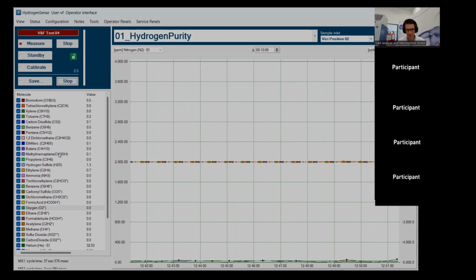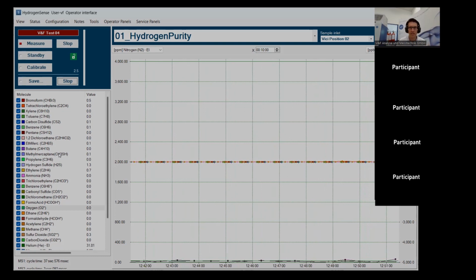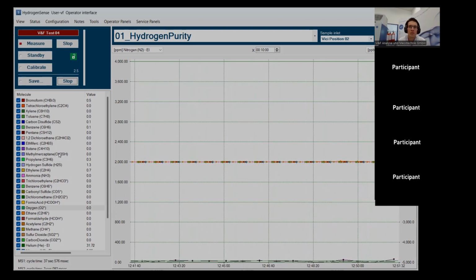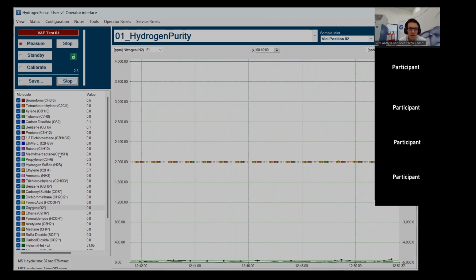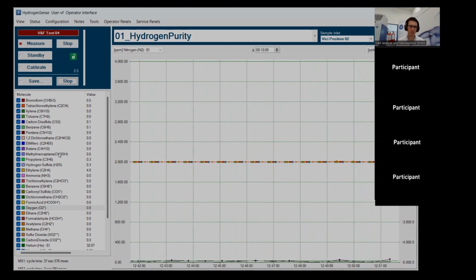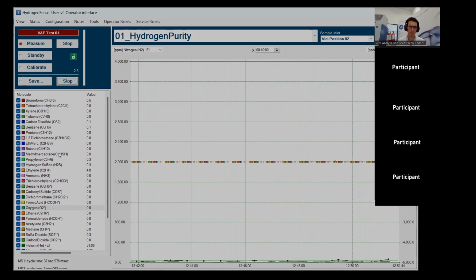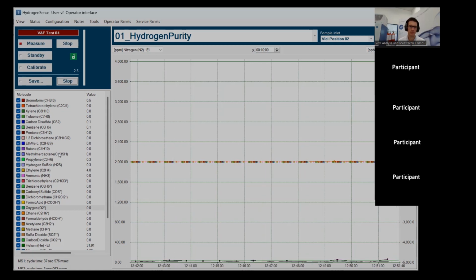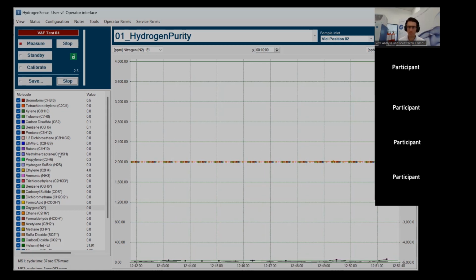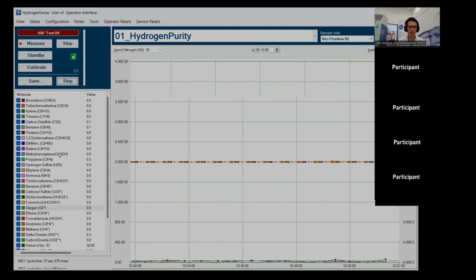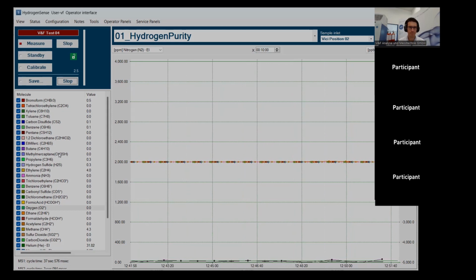And also, the accuracy and the precision of that gas will be much higher than for a very low concentration. So that's usually the way we go about getting our calibration gases. So you mean to say the high concentration calibration gases need to be purchased, and then your instrument will be calibrated with dilution with the carrier gases, maybe? No, in this case, you just calibrate it on the high concentration. High concentration. Yeah.